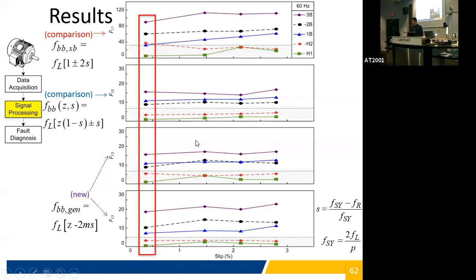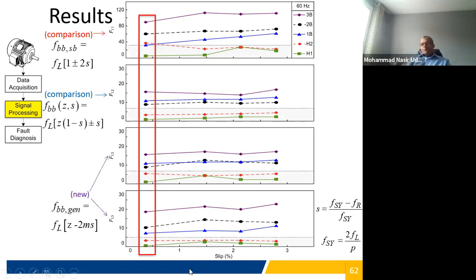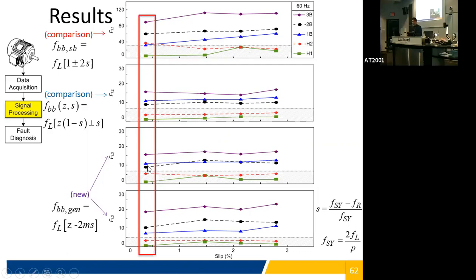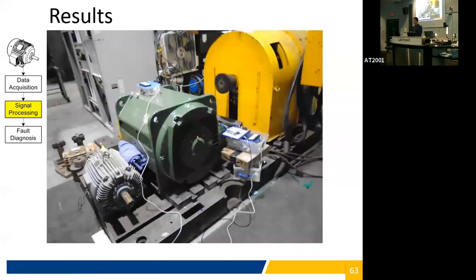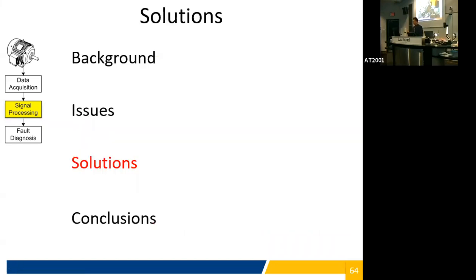And in other cases, we can see with this method, the 1-bar fault and 2-bar fault are flipped. So it would be a misdiagnosis of the severity of the fault. Whereas the proposed methods have a good balance between accuracy and the reliability of the fault index with respect to the actual fault. So the zero load condition is significant for this kind of application.